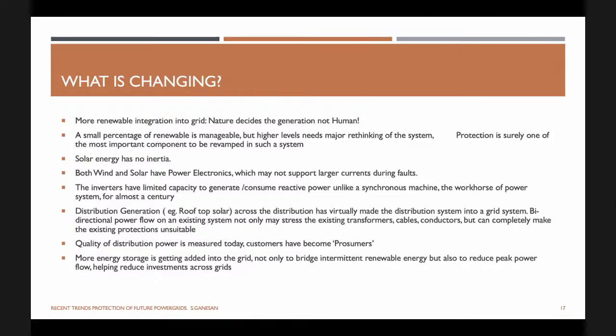The inverters, the power electronics, are sized so that you don't want to spend too much money on them. They're quite expensive even by today's standards. So whenever there's a fault, you want to protect those power electronics. Unlike earlier cases, when there was a fault, a synchronous generator, with its generator transformer in tandem, would pump in current for at least three cycles. That's not possible with power electronics dominating the scene.